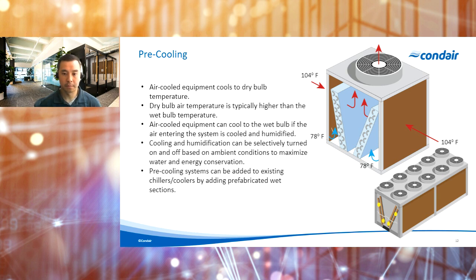So the next thing we want to talk about is pre-cooling. Well, pre-cooling is definitely not a type of data center. It's an application for adiabatic systems. Pre-cooling of equipment such as chillers and fluid coolers is not new. It's been around for many years. So we're definitely seeing an increased interest in this application due to rising power constraints in the data center industry and the shift to liquid cooling, requiring the use of chilled water systems and mechanical cooling.